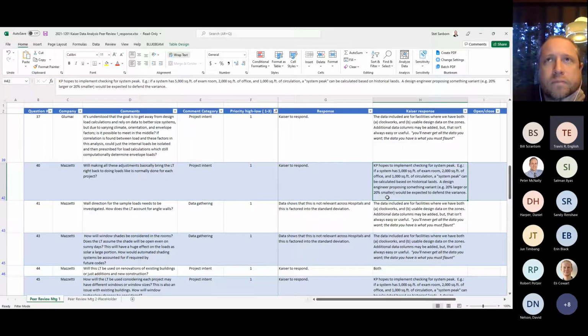Kaiser Permanente vehemently denies that energy models are comparative only. Your energy model is expected to predict the performance and states of the system that we're going to see. We load those into our acceptance criteria and actually check them during commissioning, and then for a year following, to make sure those things actually come true. That's where we're going with all this.